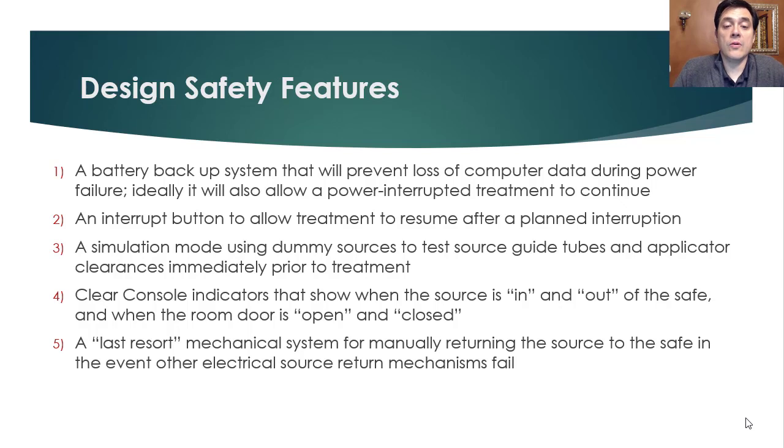There's a simulation mode using a dummy source to test the source guide tubes and applicator clearance immediately prior to the treatment. So whatever distance the source is going to travel out to, there is going to be a dummy or a test source that goes to that distance prior, to make sure the path is clear so there are no obstructions.